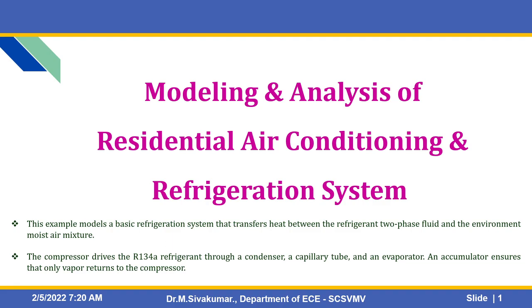This example models a basic refrigeration system that transfers heat between the refrigerant two-phase fluid and the environment moist air mixture. The compressor drives R134A refrigerant through a condenser, a capillary tube, and an evaporator. An accumulator ensures that only vapor returns to the compressor.